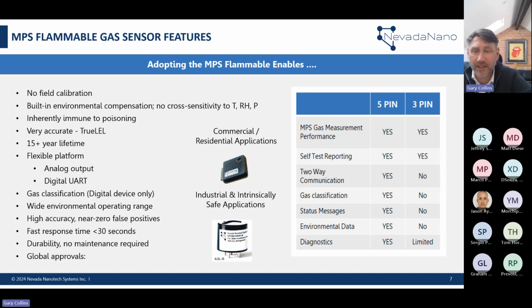The digital UART is a standard industrial UART communication, and we can share the serial comms and the detail on how to implement that. Gas classification, I'll show you some good examples there and explain how that can be valuable. It's something you see some of our clients use to articulate what sort of gases have been present at a site or during a confined space entry, for example. Because of the wide environmental range and the compensation work we do, that really reduces the false positives you might see compared to other sensors. And the actual sensor's T90 is very fast. For just one gas, that's about 20 seconds, and for a number of combustibles, it will still be below 30 seconds when you're looking at a true LEL value. So a high performing, fast responding sensor.